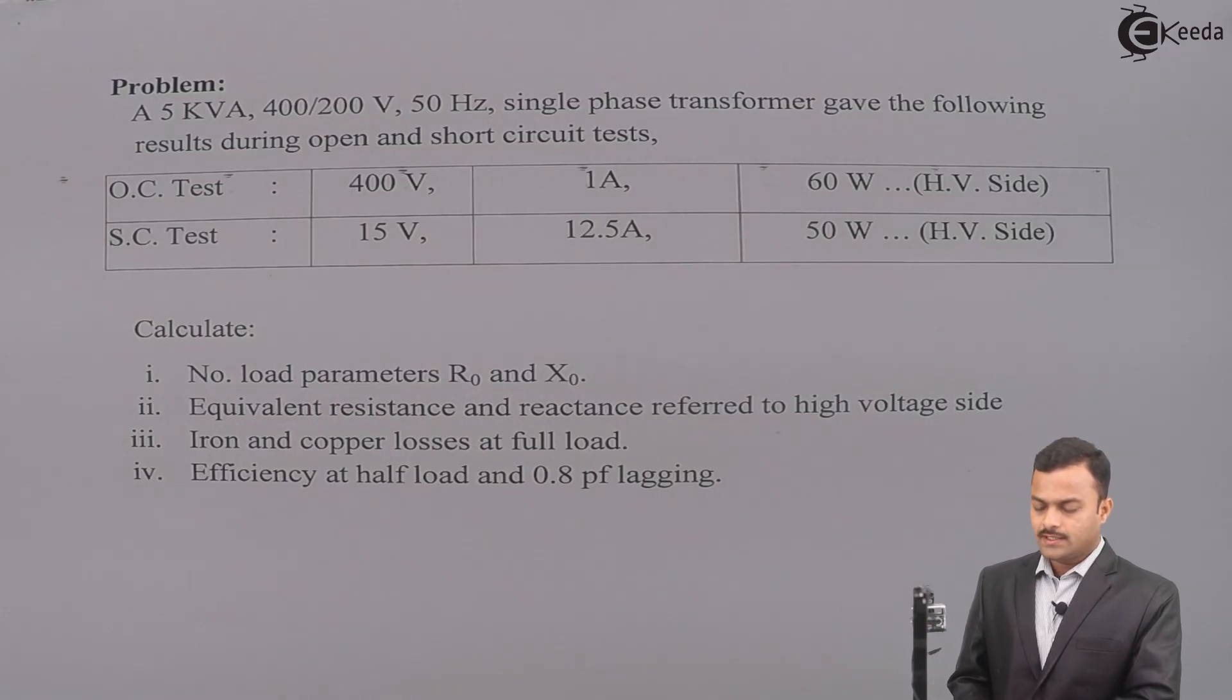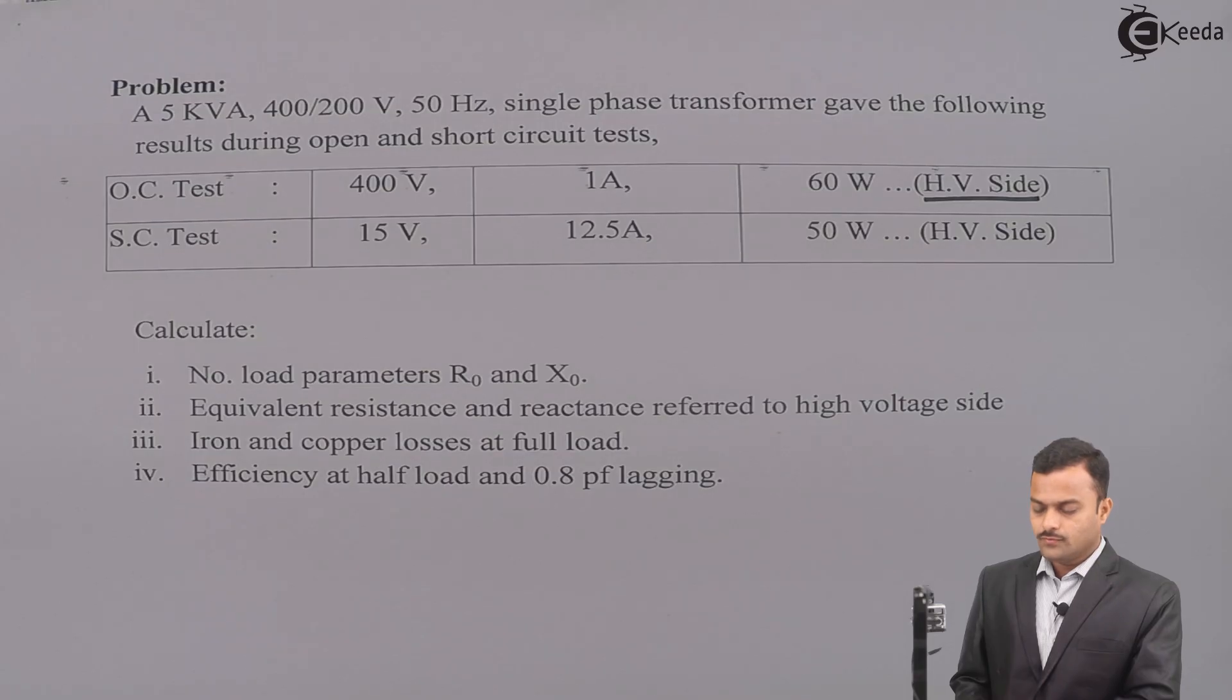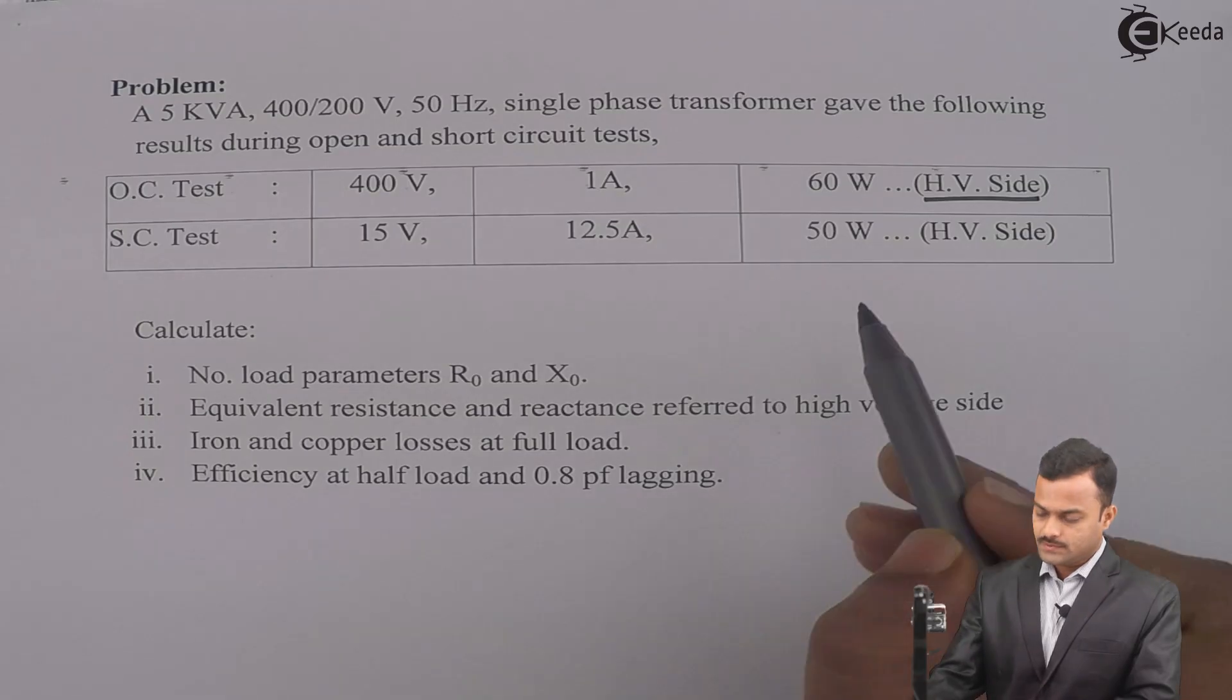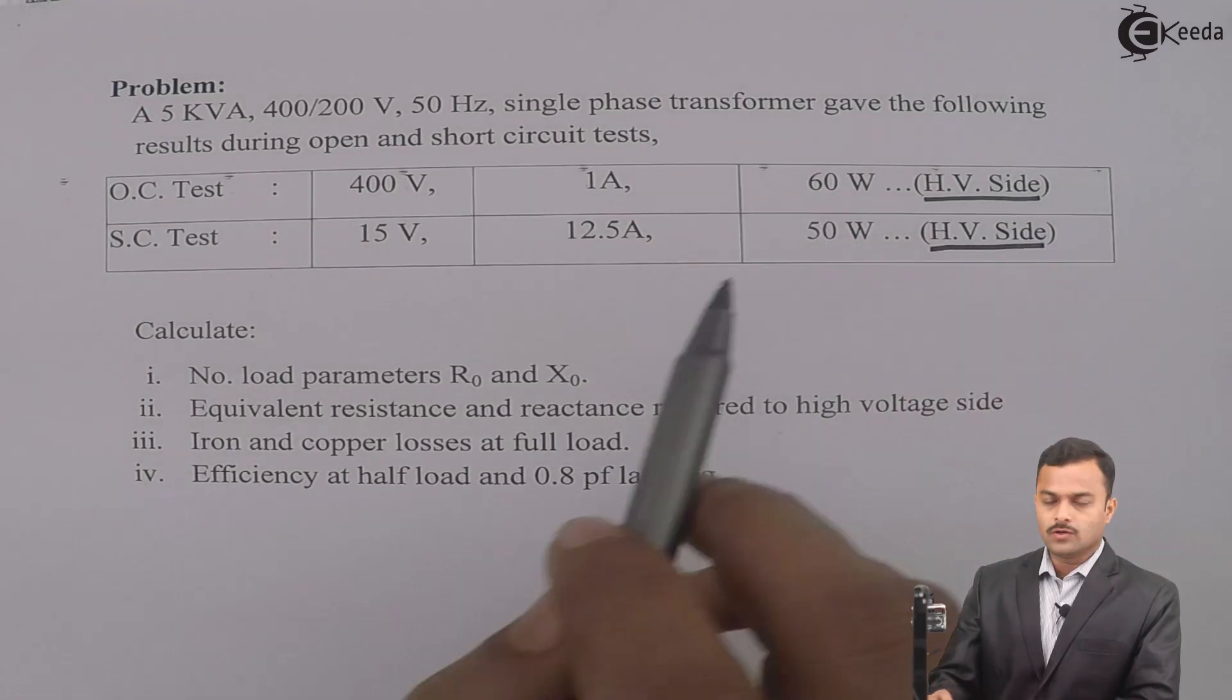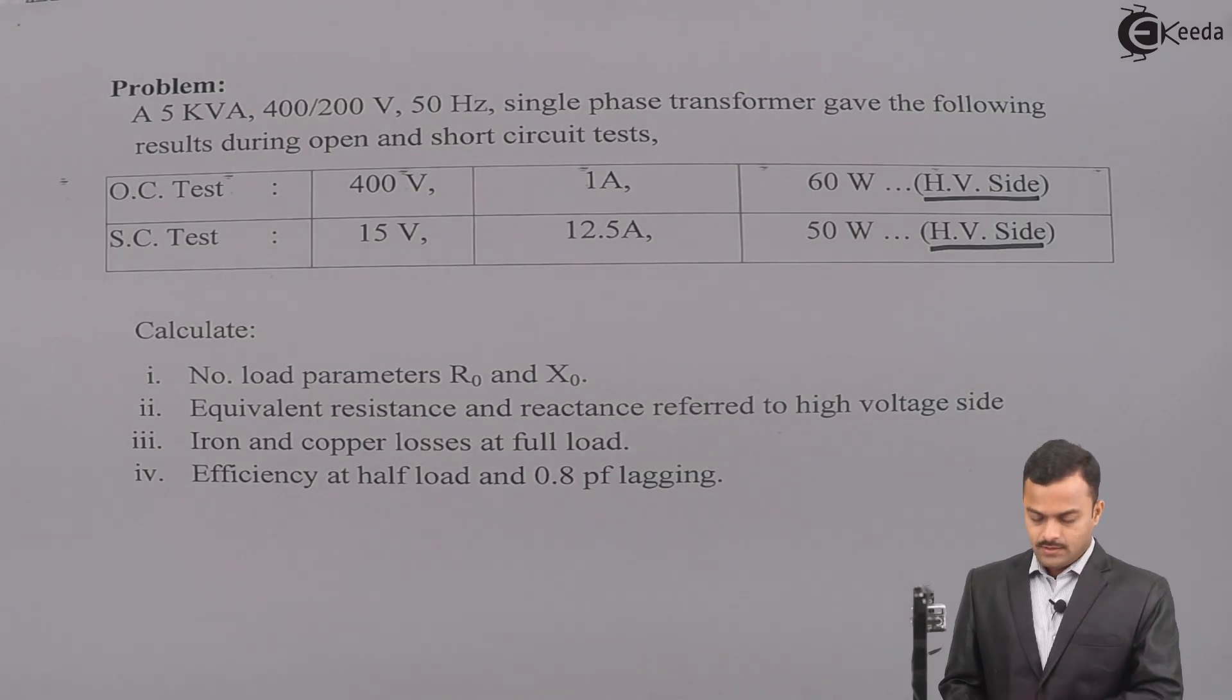Here is the problem. A 5kVA 400/200 volt 50 hertz single phase transformer gave the following results during open and short circuit test. OC test: 400 volt, 1 ampere, 60 watt, performed on HV side. SC test: 15 volt, 12.5 ampere, 50 watt. The test is performed again on HV side only. We have to calculate no load parameters R0 and X0, equivalent resistance and reactance referred to high voltage side, iron and copper losses at full load, and efficiency at half load and 0.8 power factor lagging. So, let us start.